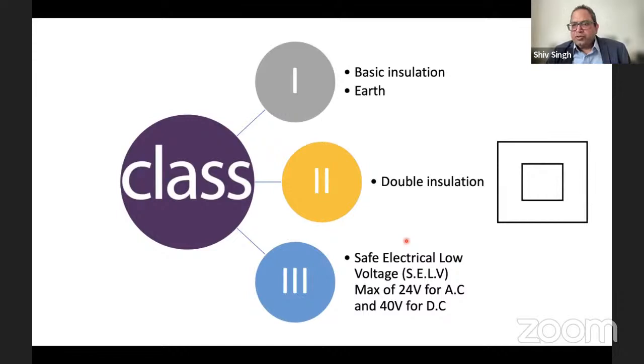And class 3 equipment uses something called SELV, or safety extra low voltage, which is a maximum of 24 volts for AC and 40 volts for DC. And because they're using low voltage, you don't actually get a shock, even if there is a breakdown of the insulation, or a wire comes off and touches it. Even if you touch them, you will not get a shock. You might feel a tingling sensation, but that's all.